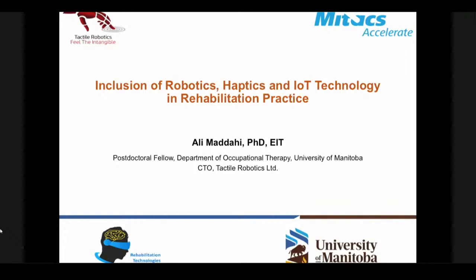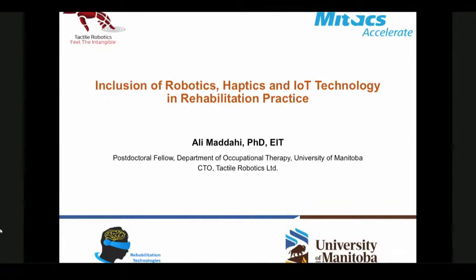The next question is from Yumi Sakamoto from the Computer Science Department. She's asking if a layperson will be able to calibrate the smart glove prior to its use. We have a kind of self-initialization and auto-calibration procedure for the sensors, so even a layperson can use the device by just pressing the power button. There is no specific or difficult procedure for calibrating the sensor.